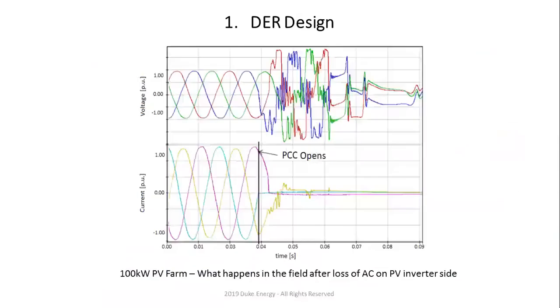Now, when you do things in the field, it's a little bit different because field devices have to be certified to IEEE 1547 and UL 1741. So what you see over here, essentially, is what happens to the PV system when the PCC opens, right? You can see that current goes down to zero at the zero crossing, and you can see the voltage actually goes up, and then everything goes down to zero, right?